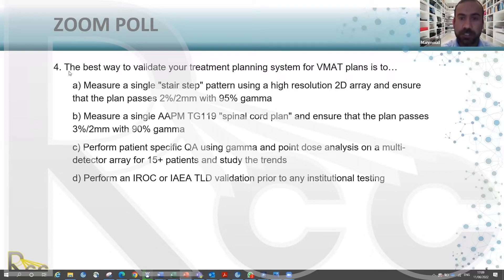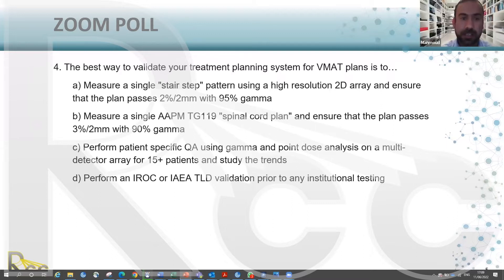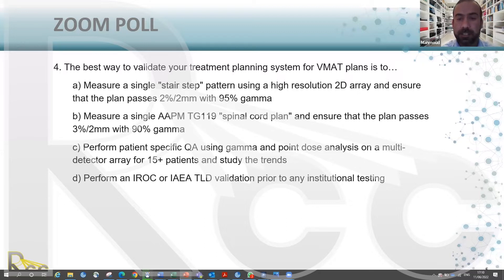A poll question: the best way to validate your treatment planning system for an IMRT plan is — A: measure a single stair-step pattern using a high-resolution 2D array ensuring the plan passes 2%/2mm with 95% gamma; B: measure a single AAPM TG-119 spinal cord plan ensuring it passes 3%/2mm with 90% gamma; C: perform patient-specific QA using gamma and point dose analysis on a multiple detector array for at least 15 patients and study the trends; or D: perform IROC and IAEA validation prior to treating.